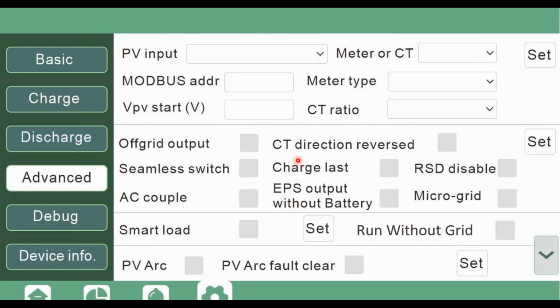Okay. Here we have CT direction reverse, which is a really cool feature where, let's say you install the CTs with the wrong direction. You can just enable this and save yourself a trip back to the installation site, and it will correct the orientation in the reading. So it's pretty awesome. Charge last. That would mean if you enable this, you would support your loads first, then your grid export, and then you would provide power to your batteries.